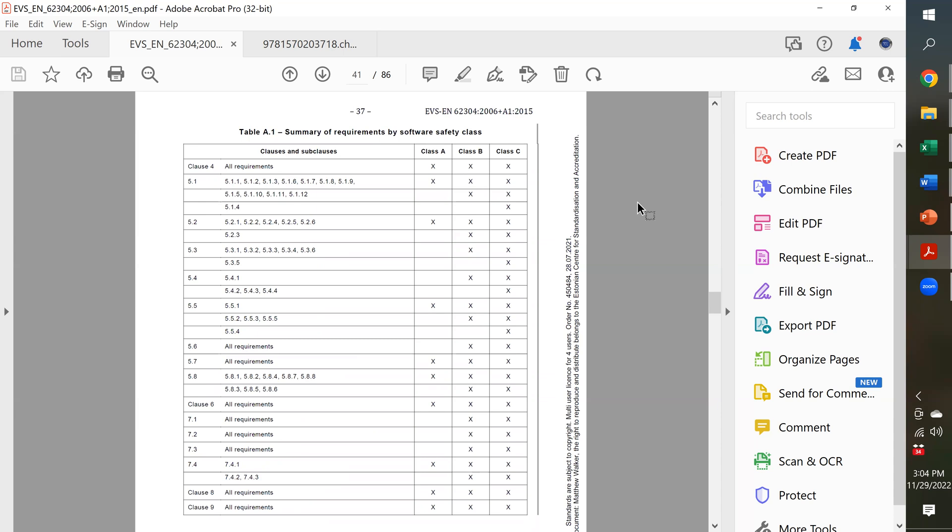But those types of devices, even an AED, the life-supporting or going to save your life, those devices are Class C. And usually, we don't run across companies that are developing a Class C software and aren't familiar with this standard. They usually already know this standard, and usually, they already know IEC TR 80002-1, and they use that as the starting point for their hazard analysis.